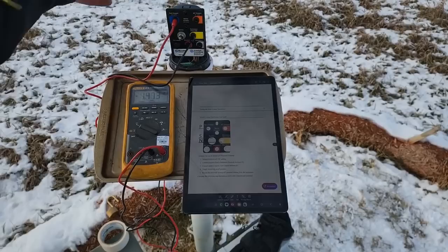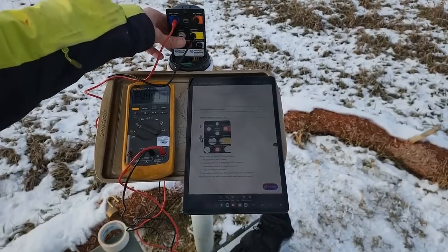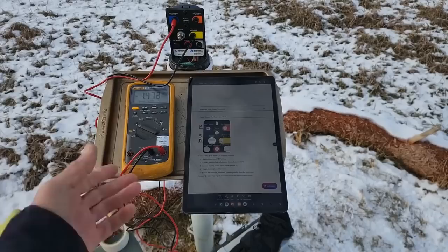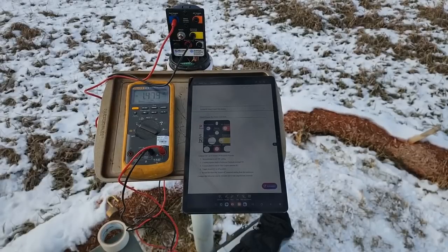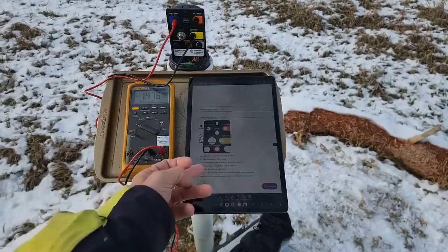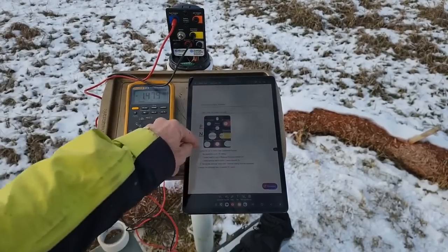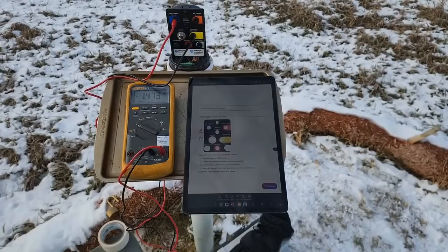It explains how to measure current. The negative goes on the structure, positive on the chemical. If the value is positive, current enters behind the coupon towards the pipe, which is desired. This means cathodic protection surrounds the coupon and current enters the pipe, which is desired. This is what the manufacturer tells us about taking measurements and connections.